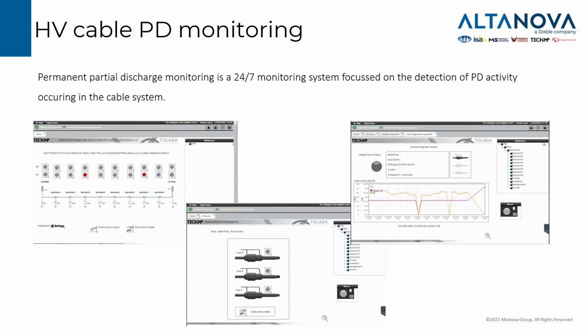It is very nice to have PD monitoring because we have a quite continuous check of the system for each detection point. We can customize alarms based on the amplitude, based on the identification of the signal, and based as well on the frequency component that we see in the signal. And everything comes out in a very nice and easy to understand web application, that is a map of the cable with the different test points and the related traffic light alarms.